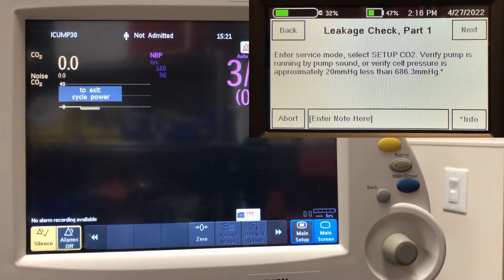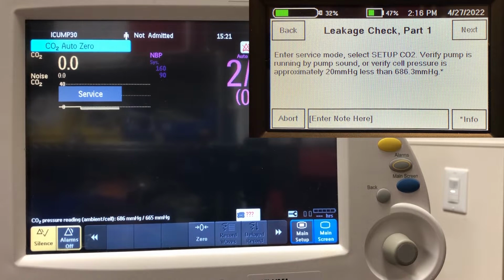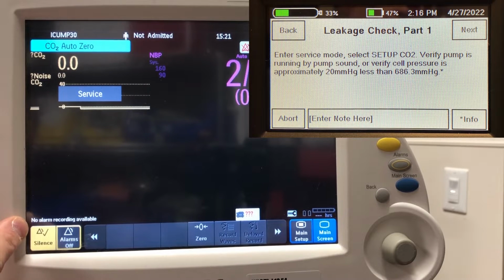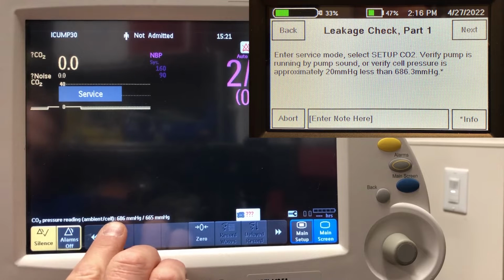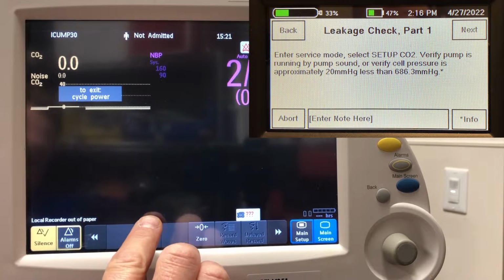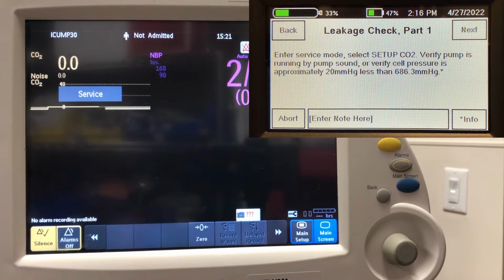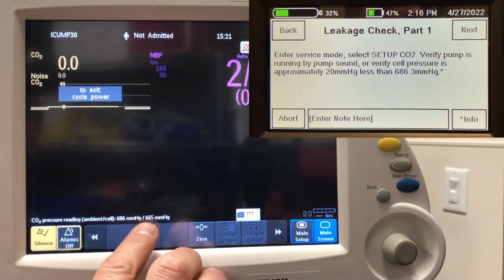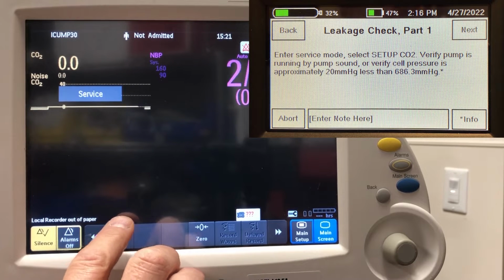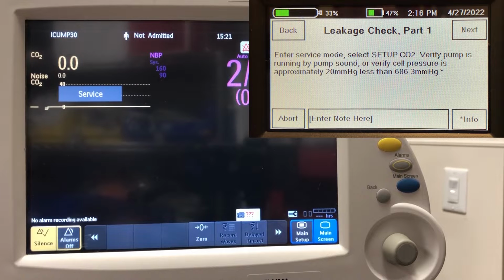So we want to verify that the pump is running. You can do that by hearing the sound of the pump running, or if you watch this scrolling message here, it'll give us the ambient pressure, and it also gives the cell pressure. The cell pressure should be approximately 20 millimeters of mercury lower than ambient pressure. That shows you that it's running.